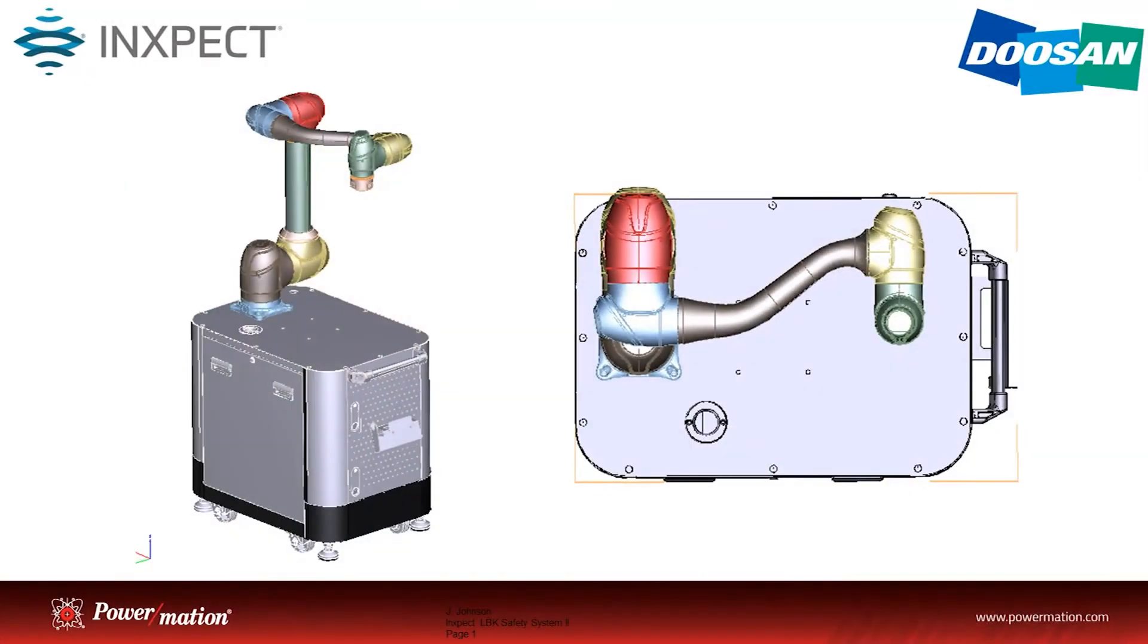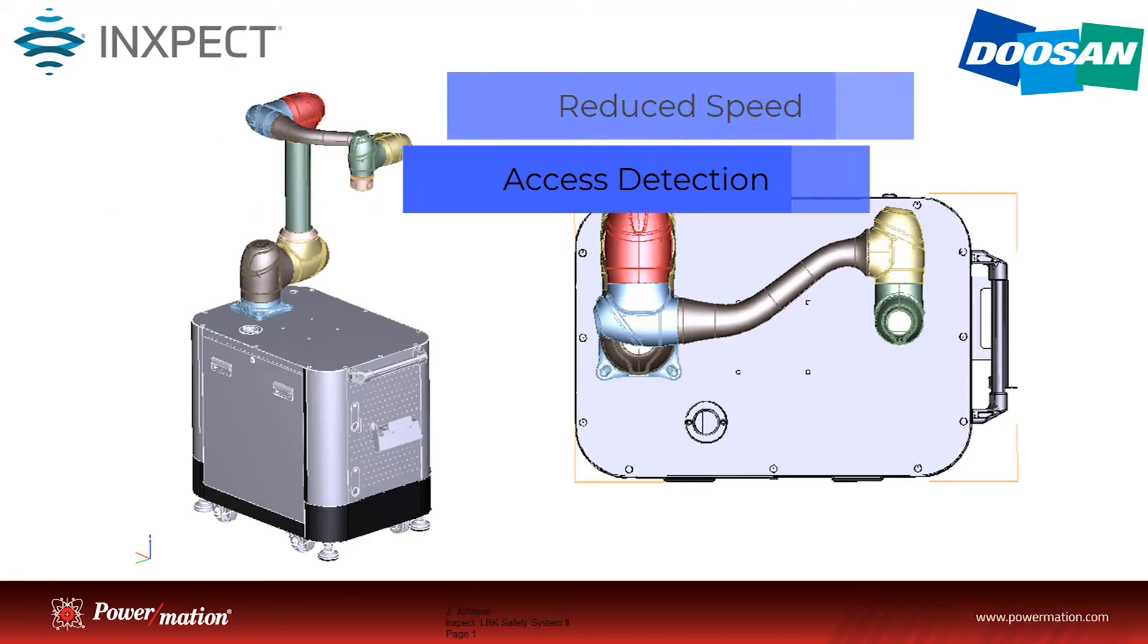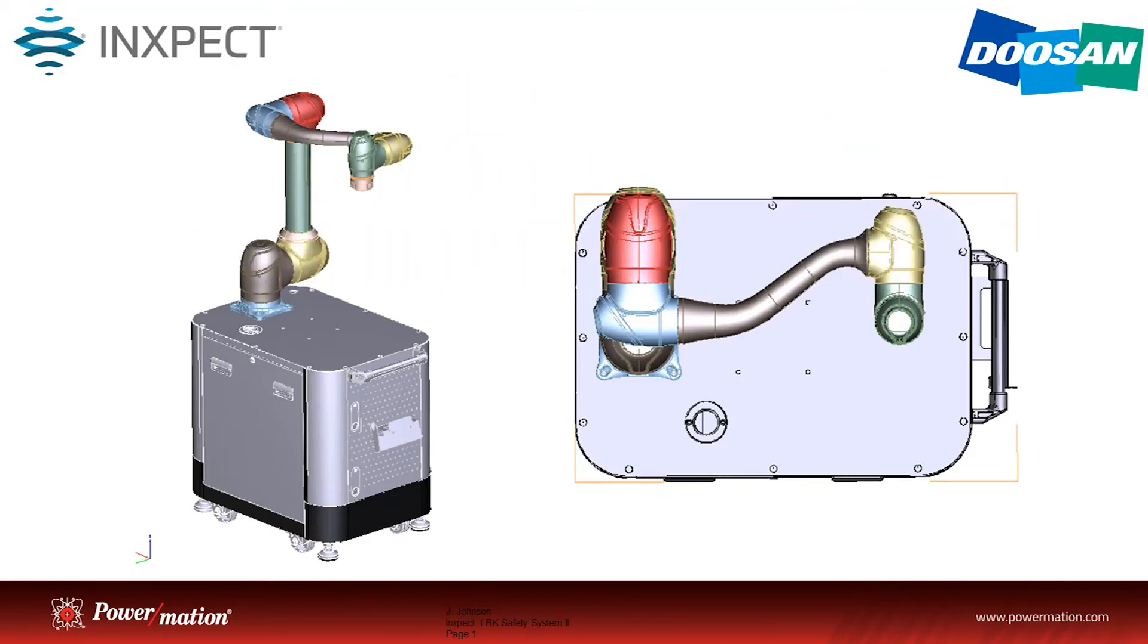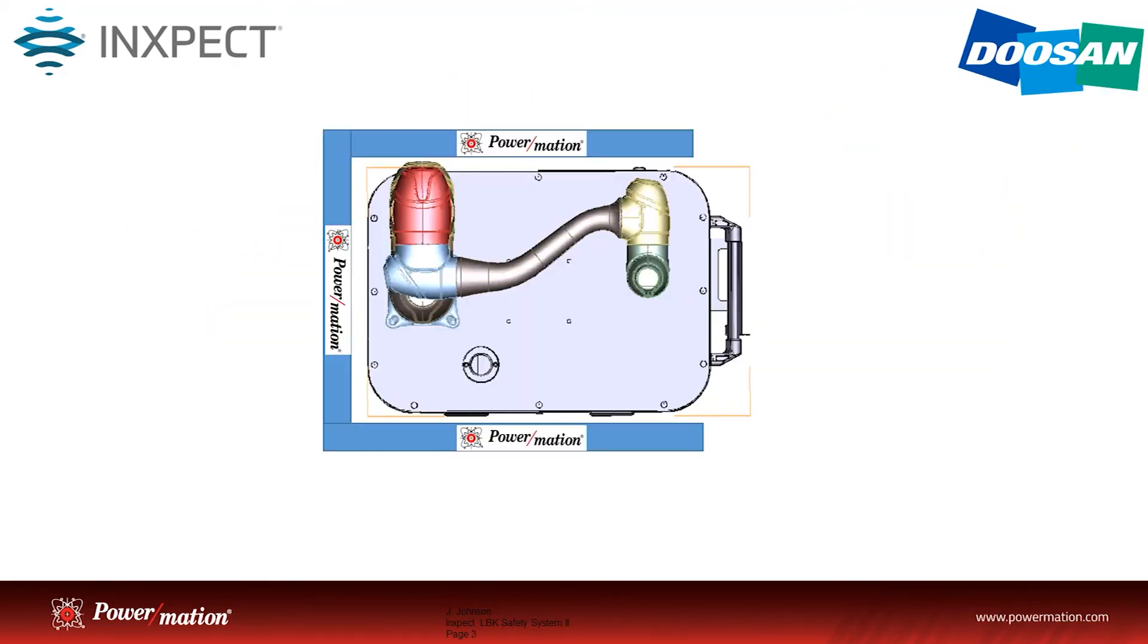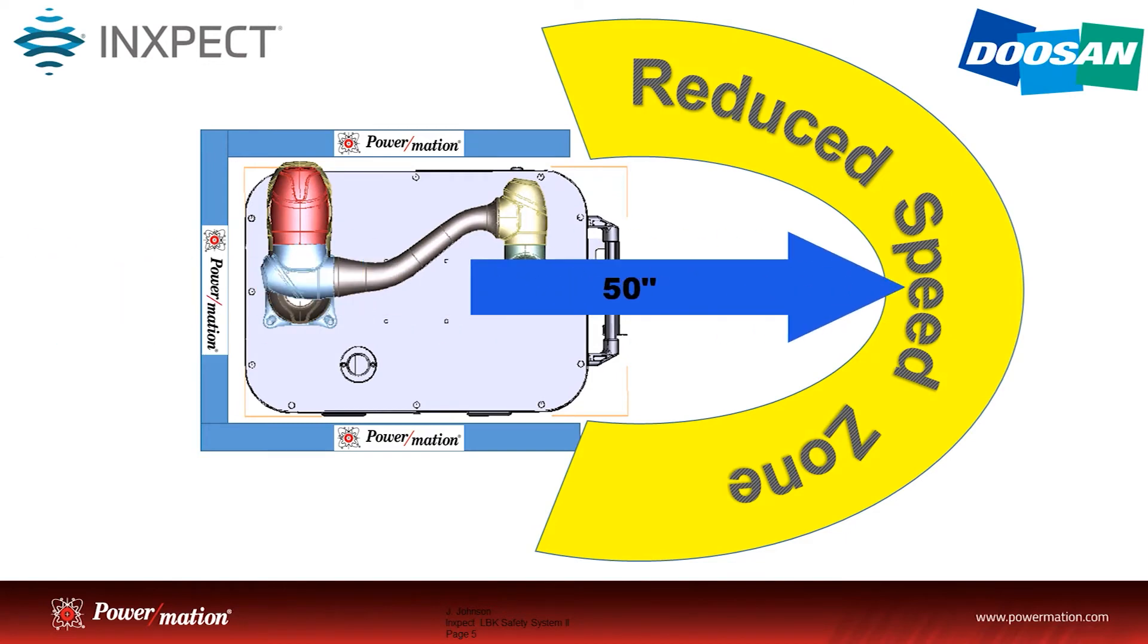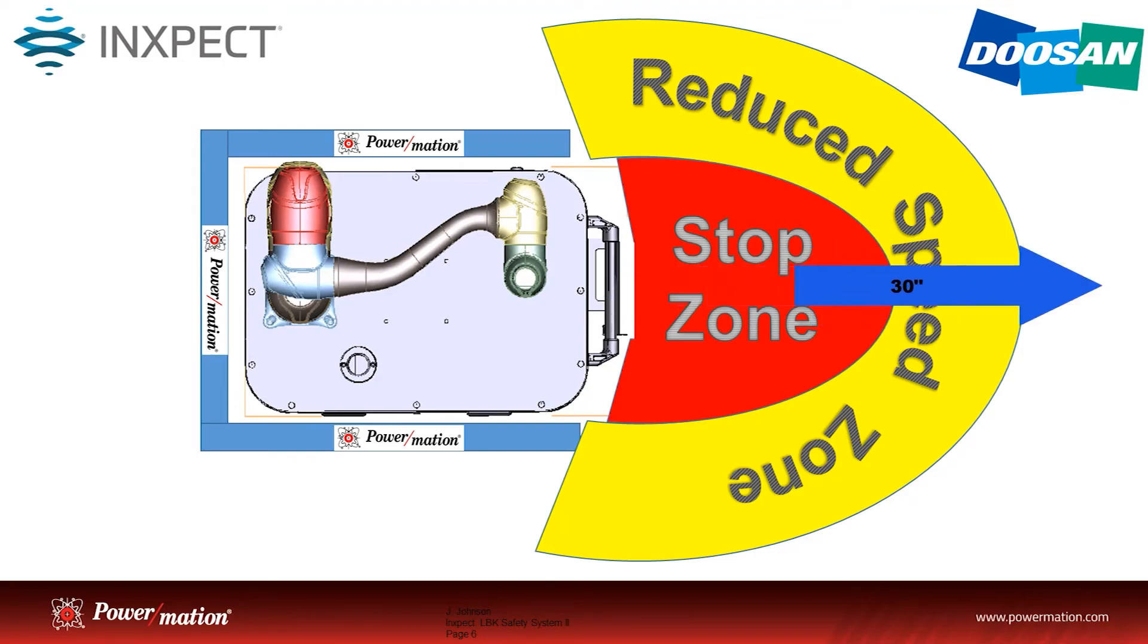For the Doosan application, let's take it one step further and show how the Inxpect system could potentially be interfaced to a Doosan collaborative robot to provide reduced speed, access detection, and restart prevention. We're going to assume that three sides of the robot are protected with Powermation fencing and only the front requires operator access for collaborative interaction. It was determined through risk assessment that we want the robot to go to reduced speed at 50 inches, and the safe stop distance was determined to be 30 inches from the center of the robot frame.